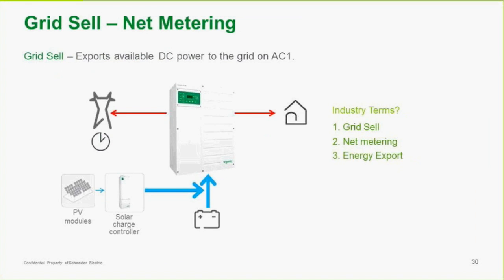So now we're going to sell to the grid. So it exports available DC power. Again, depending on all of the settings in the system, if the batteries are charged up, you can now set up the inverter to sell back to the grid. And of course, that's all subject to where you are located, what the utilities will allow you to do or not to do, and so on. So there are FIT programs. There are limitations on how much power you can sell. The XW Plus does allow you to make changes to all of those parameters, and you can set it up and hopefully recover some of your costs.